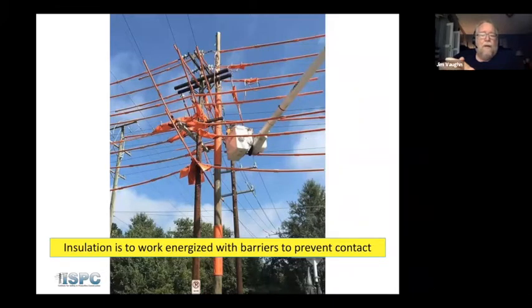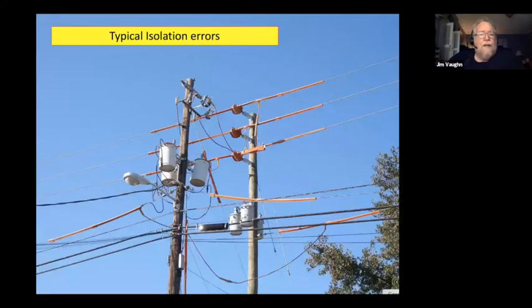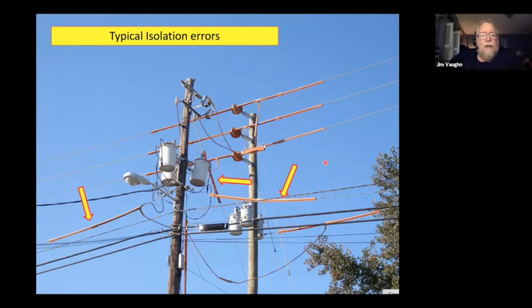And I hear people all the time say, well, we've always done it this way and it's never been a problem. And I, in my head, add up, yeah, right up until the day that it killed your lineman. So what happens is we get into a mode of drift of risk assessment, where we work for so many times and so many years and so many jobs that we start to take shortcuts and don't even realize that we are, because they worked fine last time, but they may not work right this time. This is typical of the kind of isolation errors that we make because we don't thoroughly think through what we're doing. And I'm going to try to point out a couple of things here that are missing, and I put arrows on some of the points that you need to be concerned about.